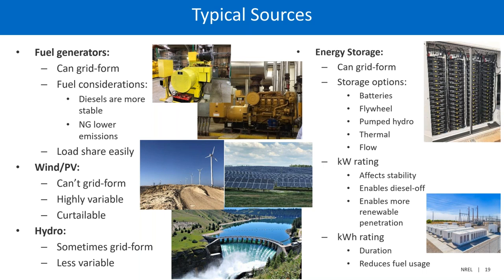Energy storage is a much different technology. It can also grid form, and there are tons of different options for how the energy is stored. Essentially it has two ratings: a kilowatt rating, which affects how stable the system is—it allows generators to turn off and allows more renewables to be on the system—and a kilowatt-hour rating, which is a duration, how long it can operate. Typically the main benefit of larger kilowatt-hours is to reduce fuel usage.